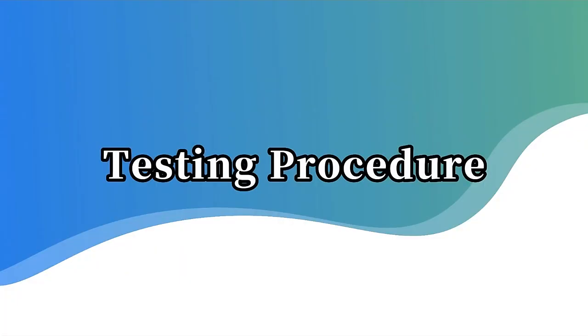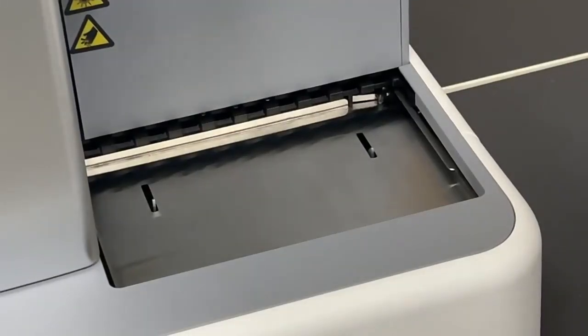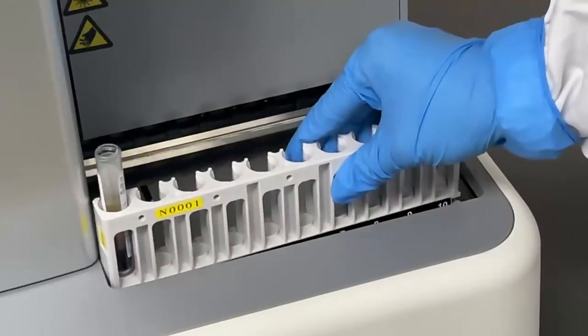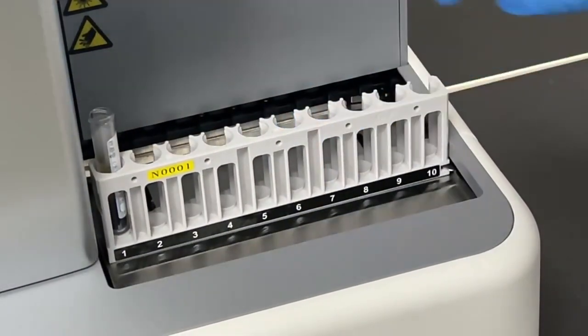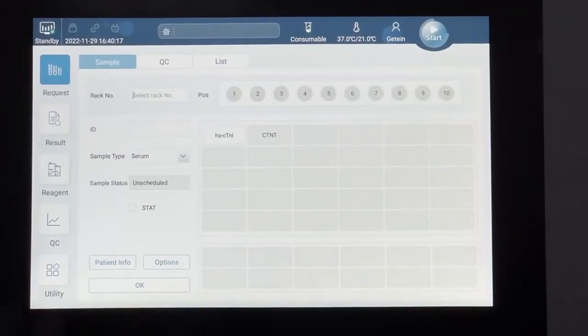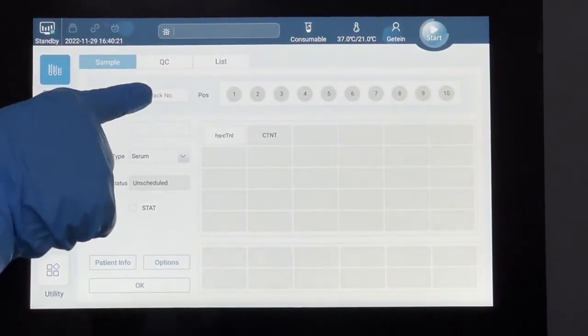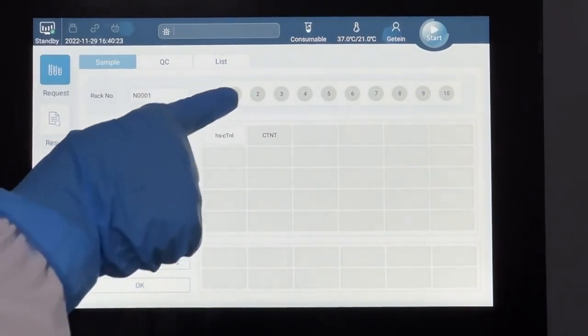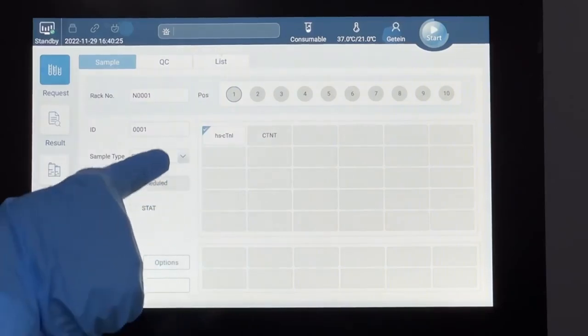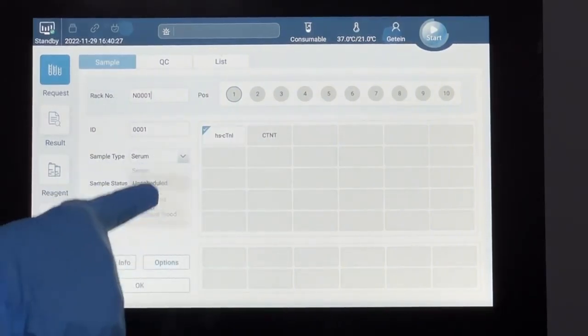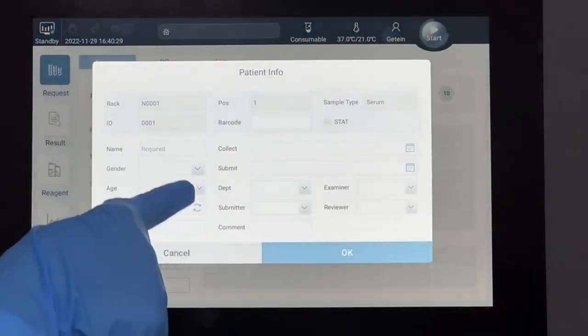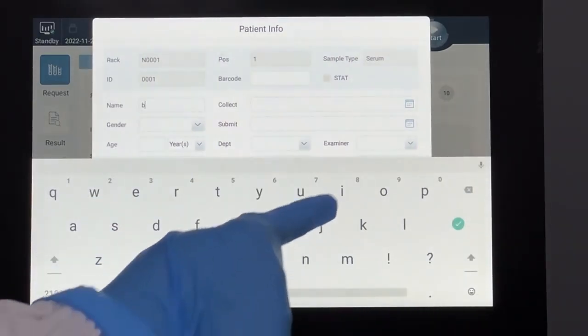Testing procedure. Place the sample on the sample rack, then place the rack in the sampling area. Select Request Sample to enter sample window. Enter sample rack number. Select the position. Select the test item and sample type. In Patient Info, you can edit the patient information.